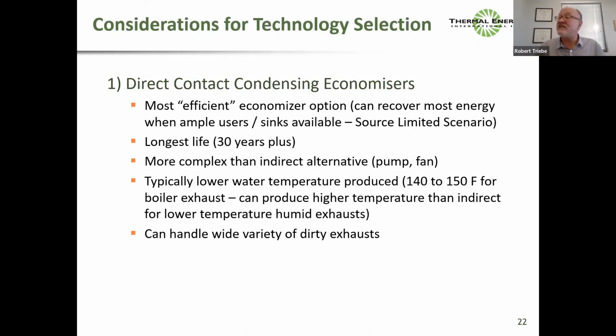And with a direct contact system, you get a lower temperature. You produce water at the wet bulb temperature. It's basically a cooling tower being used for heating. And so in a typical boiler exhaust, you can make water at 50 or 60 Celsius, 140 to 150 F. It can produce higher temperatures in a hot, humid exhaust, but I'm kind of focusing on the boiler exhaust. And in a natural gas boiler exhaust, a direct contact system will only get you about 140, 150 F, whereas an indirect system can get you higher.